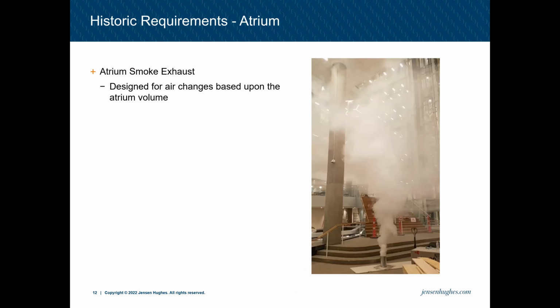Some historical requirements specific to atriums are that they weren't always designed to maintain a tenable environment. They were designed based on the amount of air changes per hour. And this changed around, I think, the 6th edition of 780 CMR. Before that, atriums were designed as what they called open wells. The volume was 600,000 cubic feet. Anything under 600,000 cubic feet required 6 air changes per hour, and anything above that required 4 air changes per hour. These usually resulted in smaller fans and smaller systems. They didn't require much makeup air.